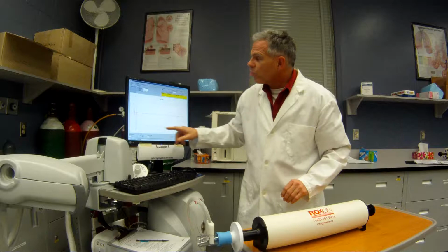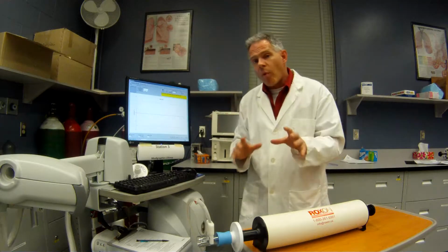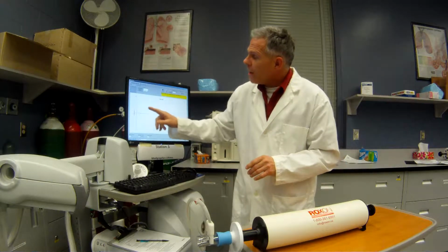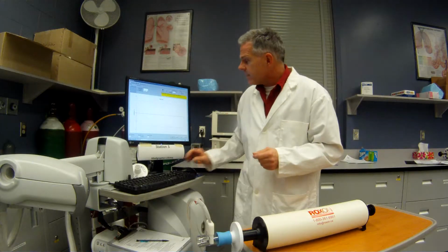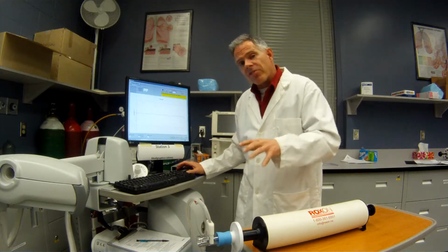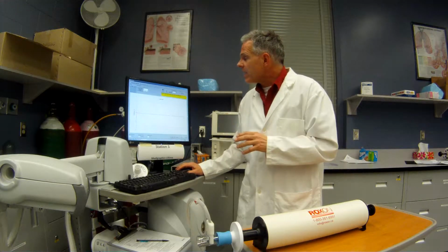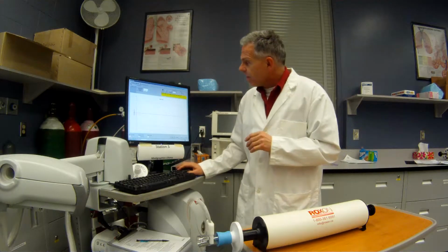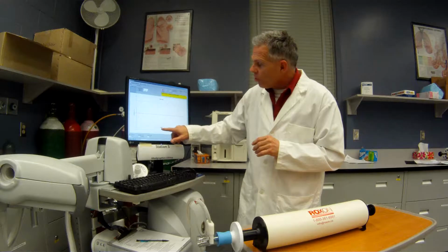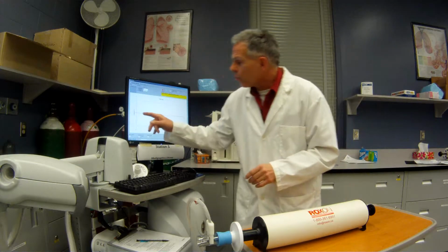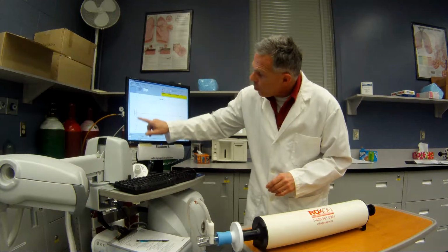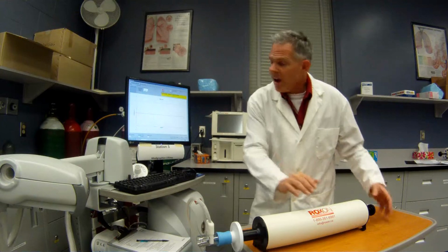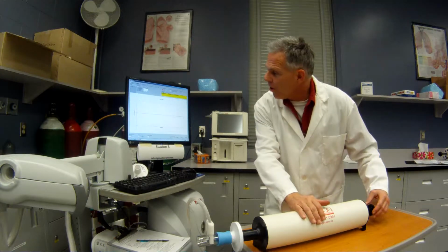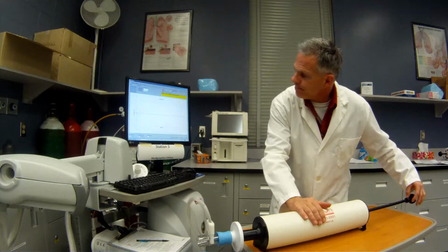Now on this little screen here, it captures some elements that are important for a calibration. We have to do it at a wide variety of flow rates. With this particular device, it actually does the calibration and verification at the same time. So we'll just hit start. Okay, and it tells me to withdraw 3 liters. Now, I've got high flow rates and low flow rates. Initially, it doesn't matter, but I start off with kind of a moderate flow rate.